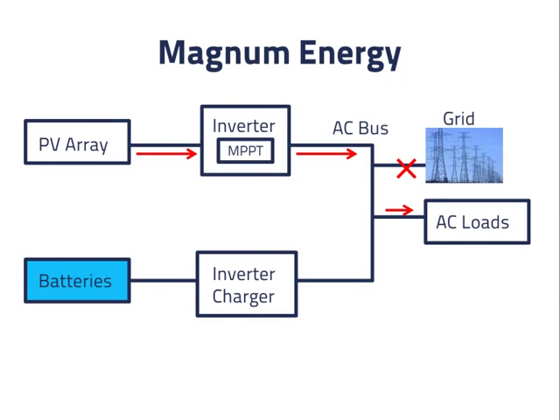So when the grid power is unavailable and the batteries are fully charged, the Magnum Energy inverter charger increases the AC bus frequency to 60.6 Hz for a short time. The increase in frequency doesn't hurt the loads, but it turns off the PV inverter from any manufacturer. The loads then derive their power from the batteries, and the inverter charger can go back to 60 Hz. After 5 minutes, the batteries will no longer be fully charged, and the inverter charger can then let the PV inverter turn back on, or block it by again increasing the frequency to 60.6 Hz for a short time.